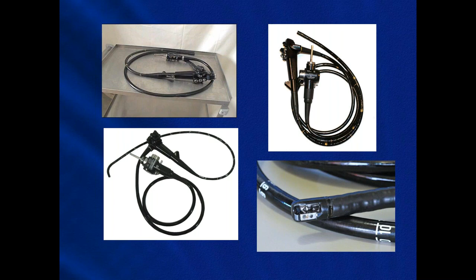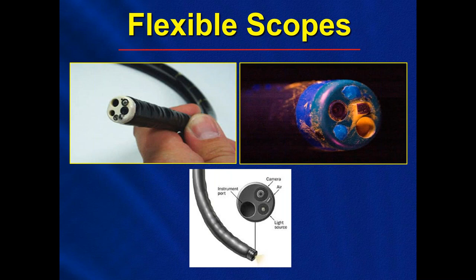So we did mention earlier about how flexible scopes are extremely challenging to clean and disinfect. Note the distal tip of this flexible scope on the left under normal lighting. On the right side is a photo of a scope after cleaning, but under special fluorescent lighting, which shows residual bioburden left on the scope that might not normally be seen by the naked eye. The takeaway point here is just to remember that just because it looks clean doesn't necessarily mean that it is clean.